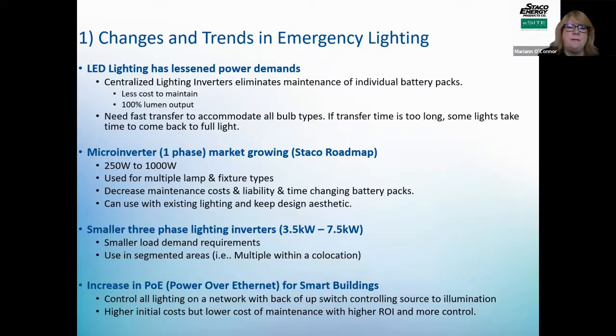In the emergency lighting industry, with the increase of LED lighting, there's lesser demand, so the loads required are less, and the lighting inverters have a lower kW rating. When we go with centralized lighting inverters, we really decrease the maintenance required compared to applications where you're replacing batteries or have small microinverters you have to check up on. All of our lighting inverters do fast transfer, so there's no lag that causes a bulb to dim and then take time to come back to full light.